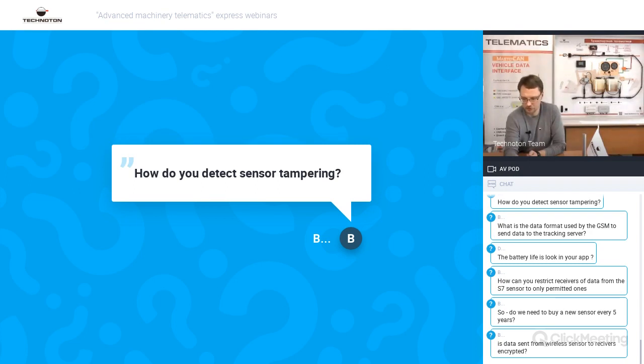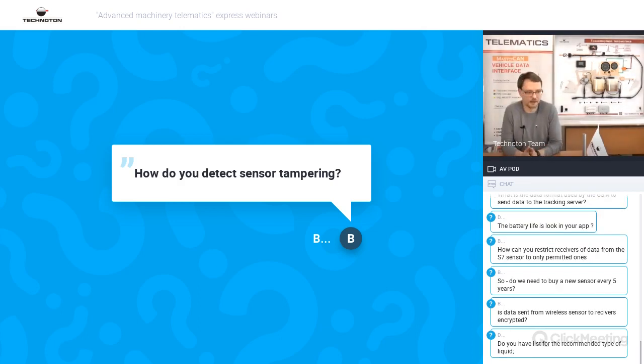Sensor tampering - could you clarify what you mean by tampering? If someone puts a magnet or something similar on top of it, nothing will happen. Nothing will change; the level sensor will continue measuring and sending data. If you mean someone trying to damage the sensor: if you don't receive data from it for several minutes or an hour, that means it's not working, and you'll need to make a visual inspection. If someone tries to block the wireless signal, and this happens repeatedly at the same place, that's obviously a sign of a tampering attempt. But there's no other way of detecting this kind of interference.